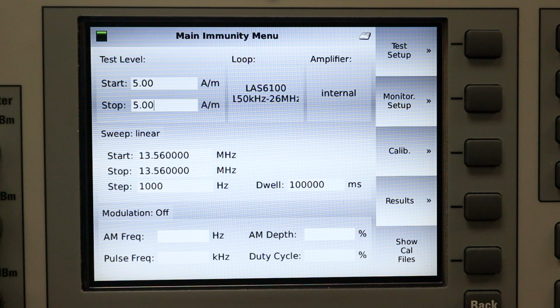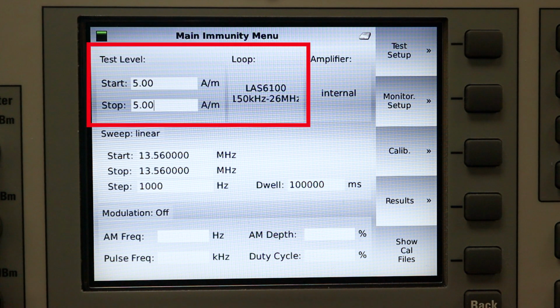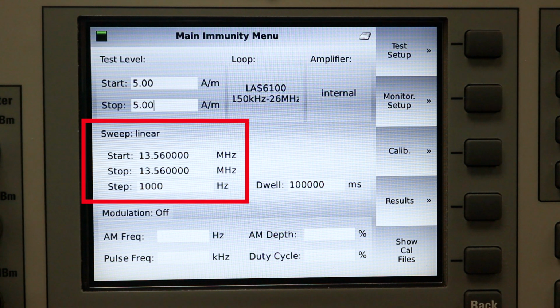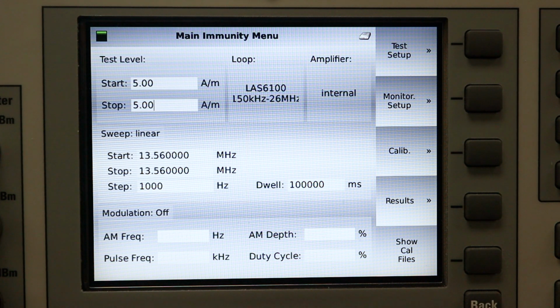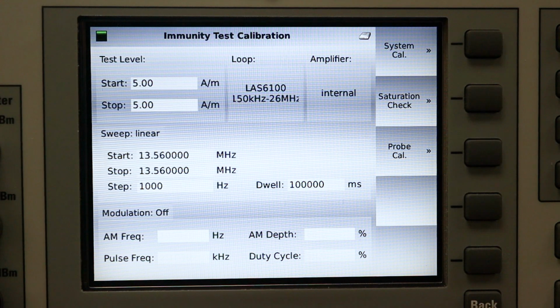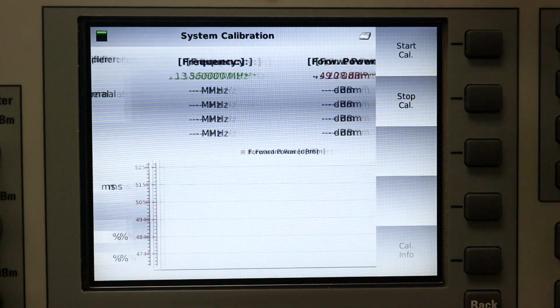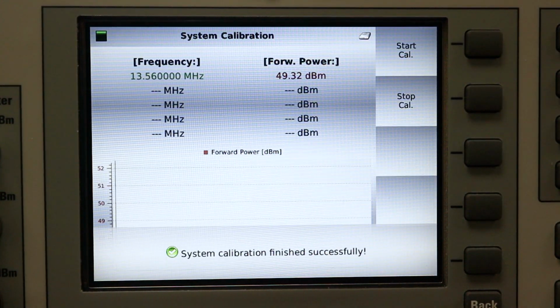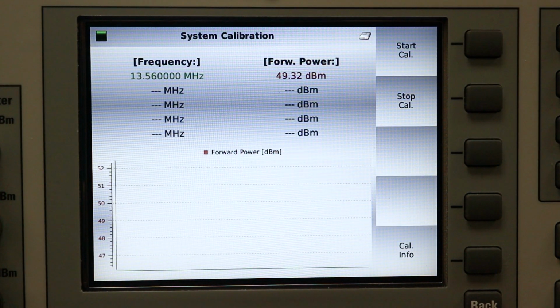Now we're back at our immunity test menu here, and we're following that same setup guidance in the user manual for the setup for 13.56 megahertz. Right now we have a test level of 5 amps entered. We have the corresponding loop antenna, and then we have our frequency range set for 13.56 megahertz. Let's hit calibration. Right now we're interested in a system calibration. Let's start the cal. And just like that, the system calibration has been completed successfully. As you can see, it's only 1 point for today's video. However, you'd follow a very similar methodology if you were doing multiple points.